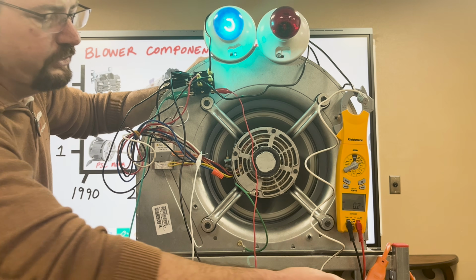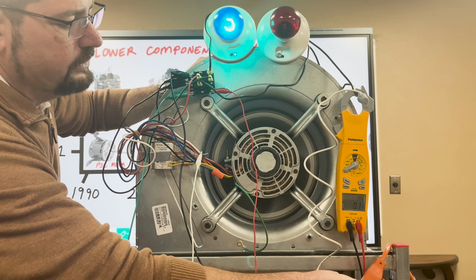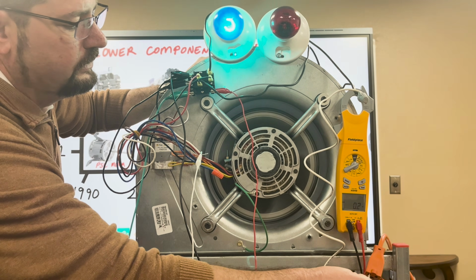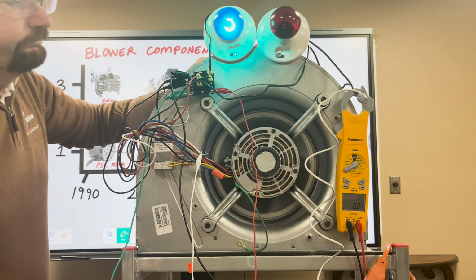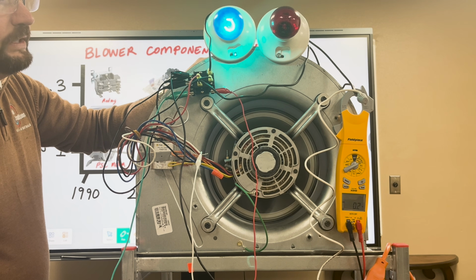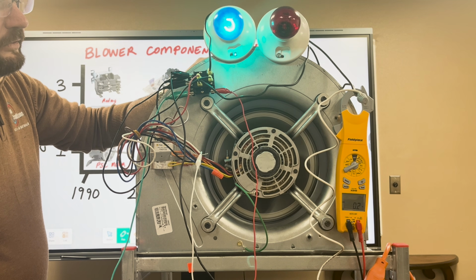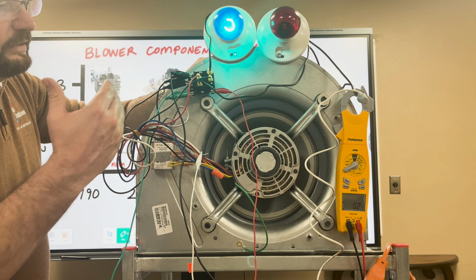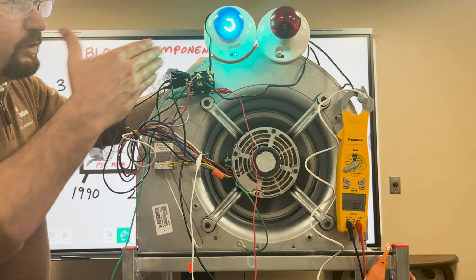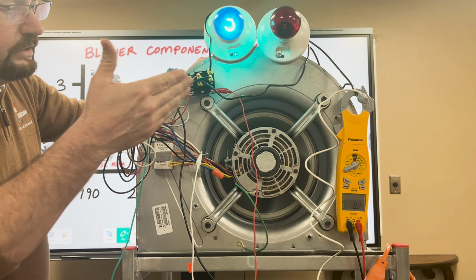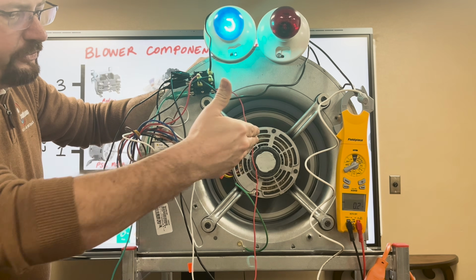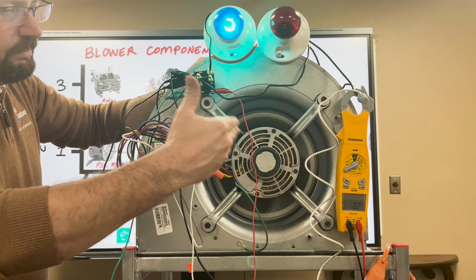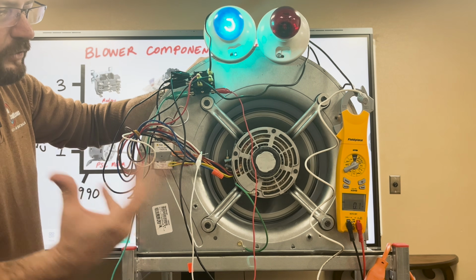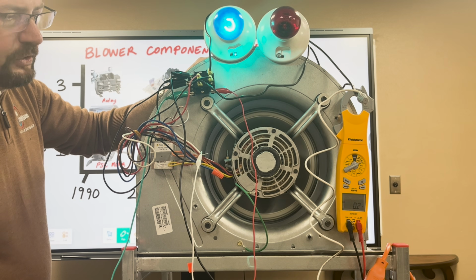Again, this neutral is the reason why my lights are coming on. So if I were to take neutral out, we'll lose our path. We're using this relay to take a leg of power, run it through one load and back to neutral, take a leg of power, run it through a second load, and with the other leg of power, have a full 240 volts to energize a 240 volt load.